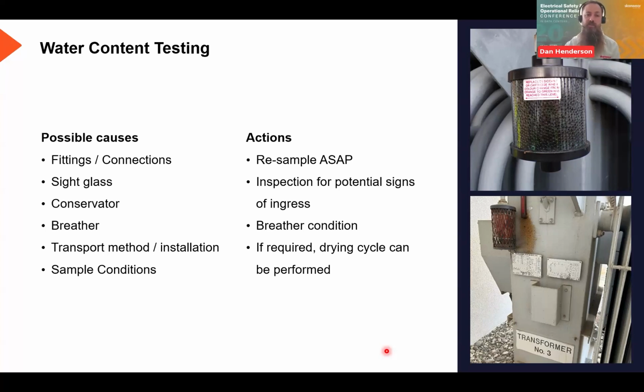And then the key outputs typically are to inspect the asset and see if you can identify signs of the ingress, the breather condition, as we've mentioned. And if you can identify it, as a mitigation you can go to a reputable oil company and they can cycle the oil, where we can take the asset offline and cycle the oil through a drying process and reduce that moisture through coalescers and pre-filters, and with heat, to then put it back in a reconditioned state.